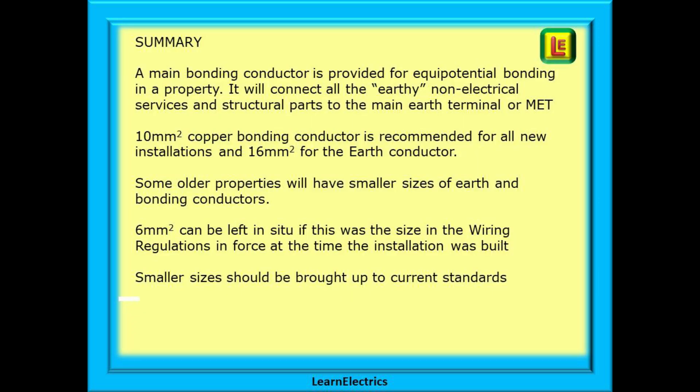A main bonding conductor is provided for equipotential bonding in a property — it will connect all the earthy non-electrical services and structural parts to the main earth terminal or MET. 10 mm copper bonding conductor is recommended for all new installations and 16 mm for the earth conductor. Some older properties will have smaller sizes; for a TNS system 6 mm can be left in situ if it was the size specified in the wiring regulations in force when the installation was built and the cable will carry the prospective fault current for the property. Smaller sizes should be brought up to current standards.